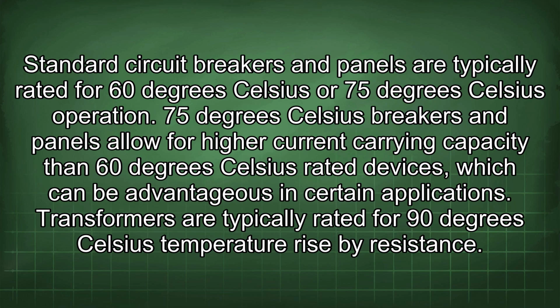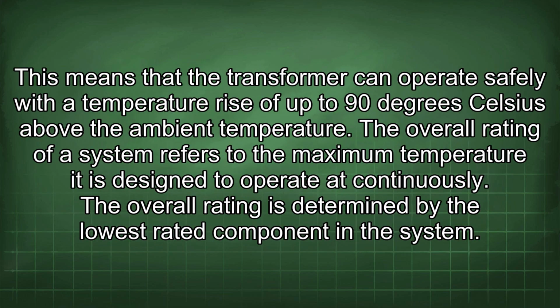Transformers are typically rated for 90 degrees Celsius temperature rise by resistance. This means that the transformer can operate safely with a temperature rise of up to 90 degrees Celsius above the ambient temperature. The overall rating of a system refers to the maximum temperature it is designed to operate at continuously. The overall rating is determined by the lowest rated component in the system.